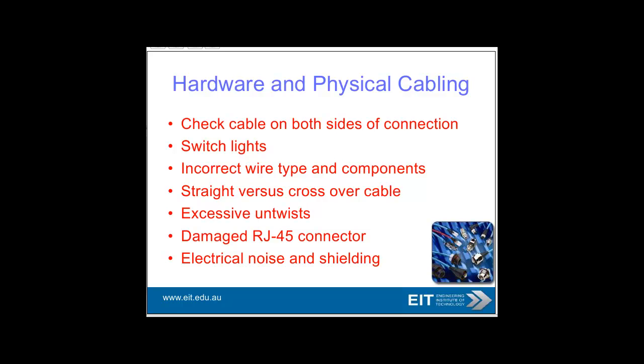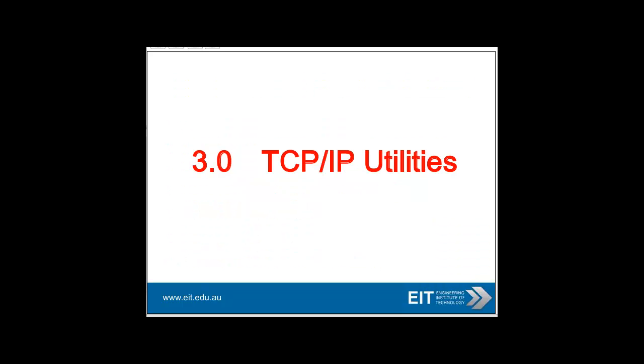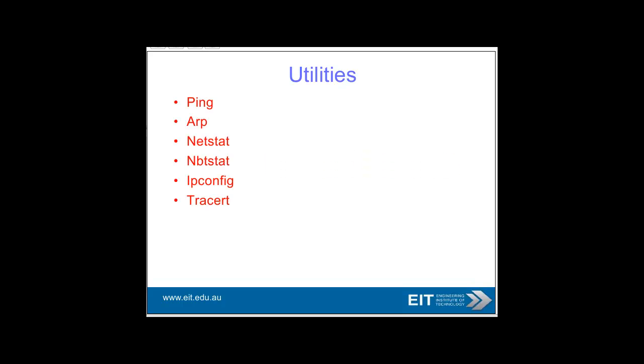I had a problem recently with a brewery, and we couldn't configure a switch. It was all wired up correctly. But a subtle problem — which is not on that list — was the power supply. The power to the switch had actually dropped below the required level. It was an industrial switch requiring 24 volts, but the voltage had sagged to 20 volts. The switch was still operating, but as soon as you connected a new device onto the switch, it wouldn't recognize it. Only when you reset the switch would the problem go away. We eventually found out the power voltage levels were low — and that would not have been picked up otherwise. It comes with experience; a rather painful way of learning, but a very memorable one.